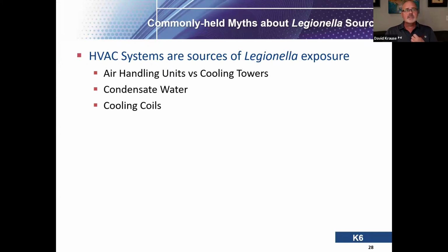One myth is that HVAC or air conditioning systems are sources of exposure. Many people equate this to the air handling units inside buildings and the condensate or cooling coils, and some publications have recently stated this with no evidence or basis. The conditions just aren't right for Legionella to grow there. It's the cooling towers, the outside components of an HVAC system, that are the real concern. So that's one myth we need to decouple.